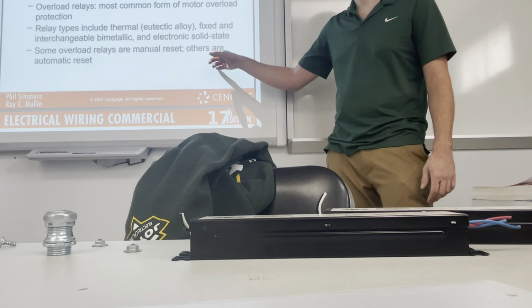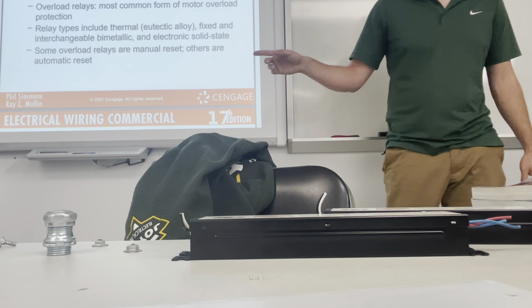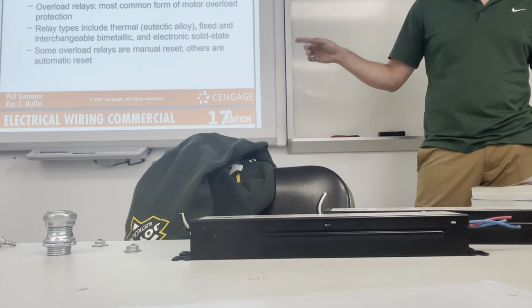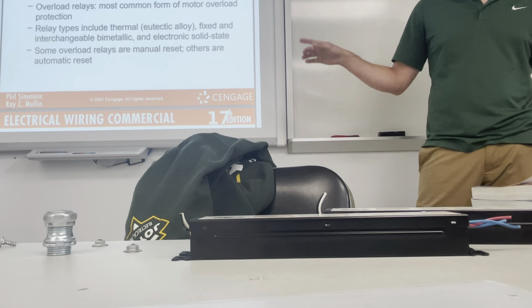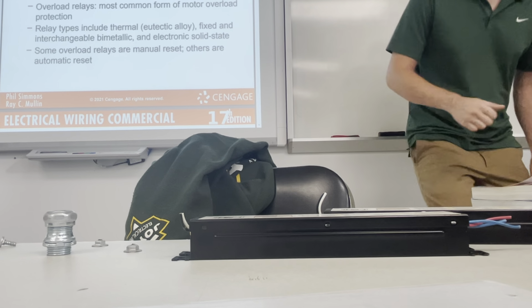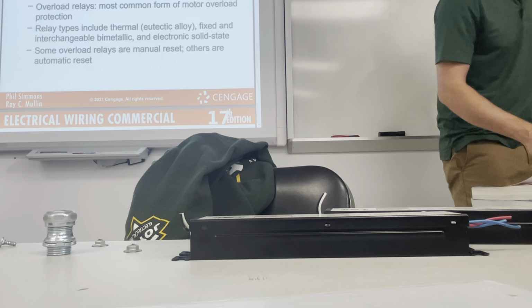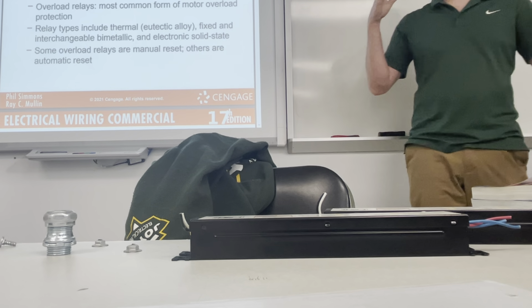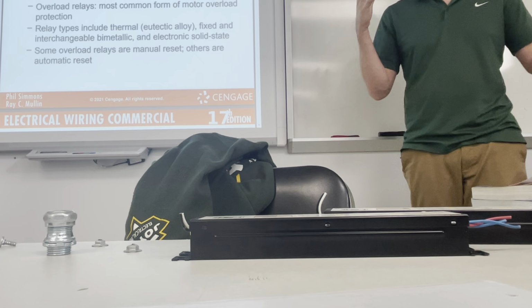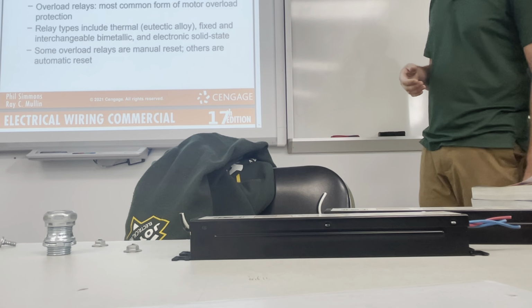However, if you're in a pumping station for a sewer and that motor gets too hot, I would much rather let that motor cool off a little bit and turn back on versus somebody climbing down to that sewer every time and hitting a manual reset. Do you see how different objects can be used in different situations? Good.